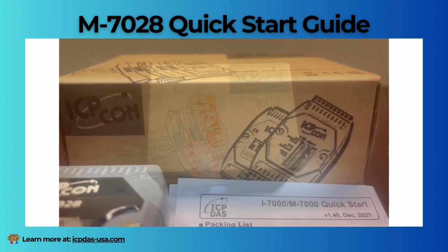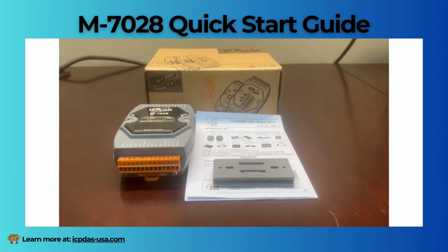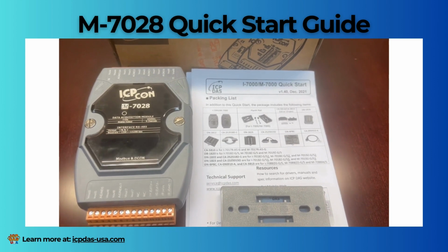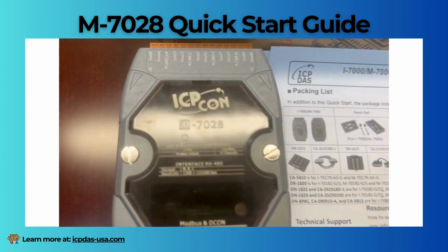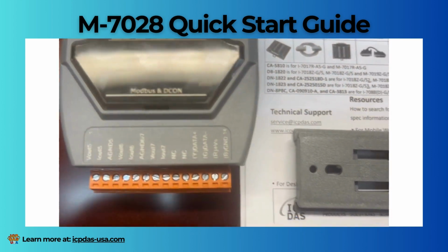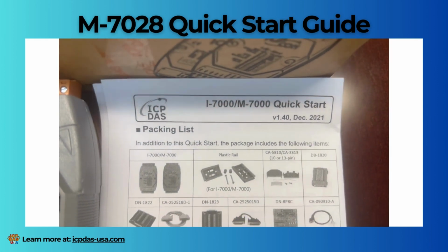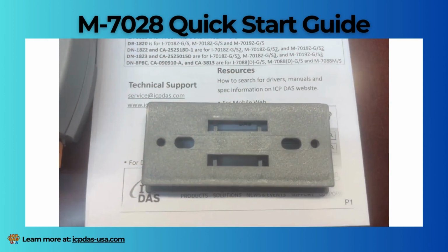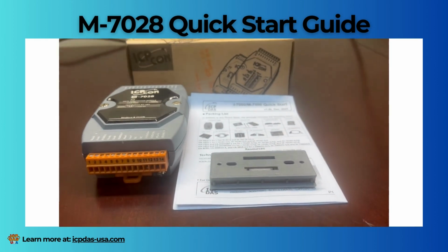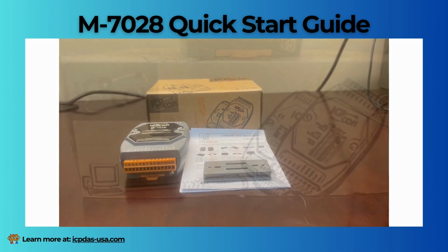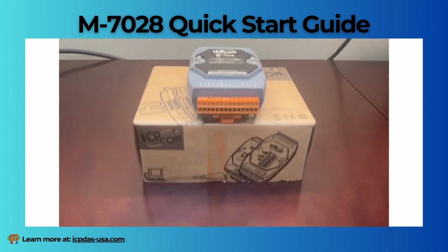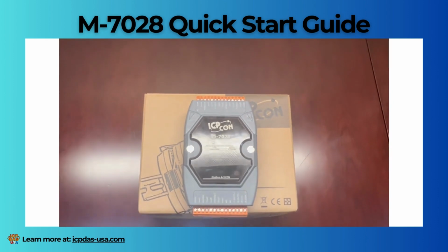In today's video, we are covering the Modbus RTU 8-channel analog output M-7028. The analog output channels on this module can be configured for 0 to 5 VDC, ±5 VDC, 0 to 10 VDC, ±10 VDC, 0 to 20 milliamps, and 4 to 20 milliamps.